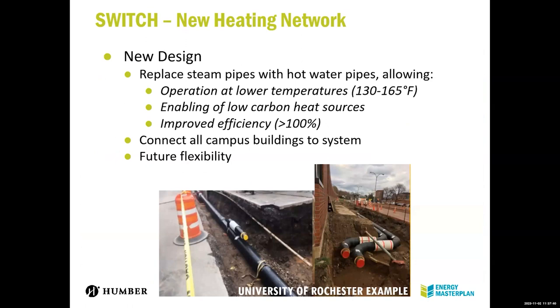Okay, so now getting into the new design. Switch is going to be demolishing all of that existing steam system and network and replacing it with a completely new hot water piping system. With the hot water system, we can operate the network at much lower temperatures, down into that 130 to 165 Fahrenheit range. With the lower temperatures, we'll have much more flexibility in how we produce that heat. Since our grid is so clean in Ontario, our focus for the project was to electrify the plant heating as much as we possibly could.